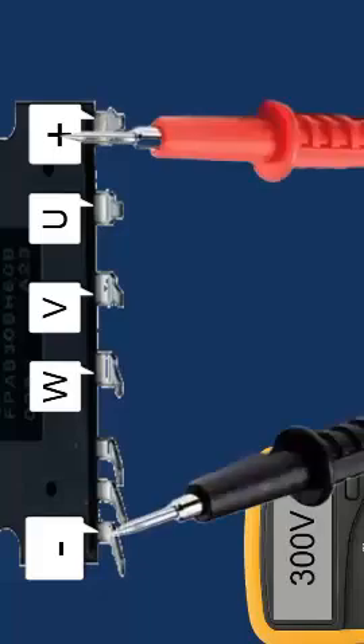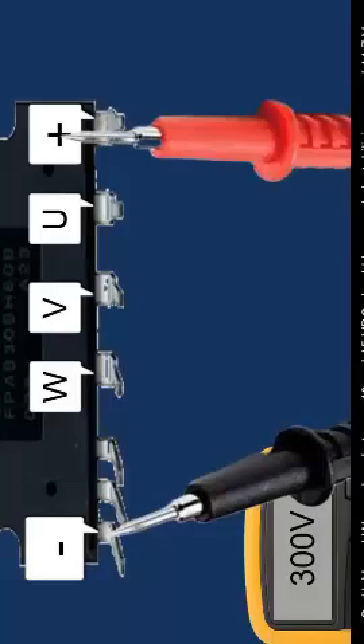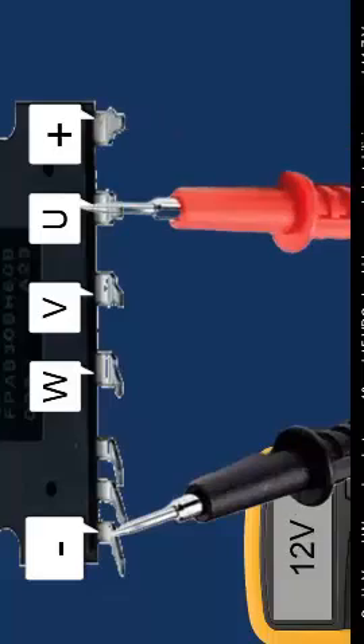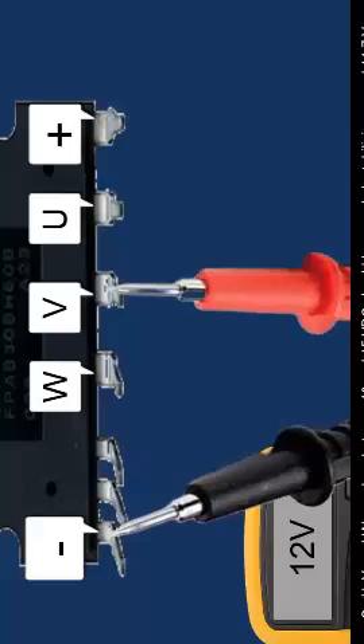Typical tests. Measure between positive and negative. It should be between 300 and 320 VDC. On U, V, and W, values between 10 and 15 VDC should be recorded, stabilizing around 11.7 volts depending on the manufacturer. Characteristic failure case.